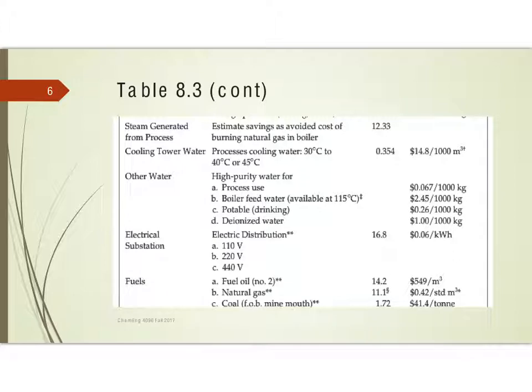We also have cooling tower water, which is cooled by air to 30 degrees C and returned from the process at 40 to 45 degrees C. Then we have water needed for other uses within the process: boiler feed water, which is going to be more expensive because we're adding chemicals to that water to keep it from destroying our boilers. We need drinking water and sometimes we're going to need deionized water. The cost of each of these is different as reflected in this table.